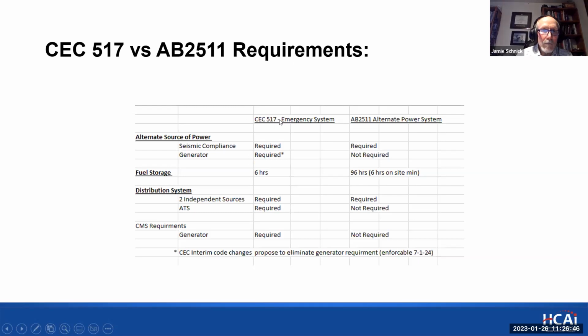What I really wanted to point out is that the 517 requirements actually exceed the requirements we see in the new AB 2511, but not by a lot. 517 requires seismic compliance for your emergency power source, and AB 2511 also requires that. 517 requires a generator today in current code as written; AB 2511 does not require a generator. 517 requires 6 hours of fuel, and AB 2511 has a stricter requirement, provision for 96 hours.